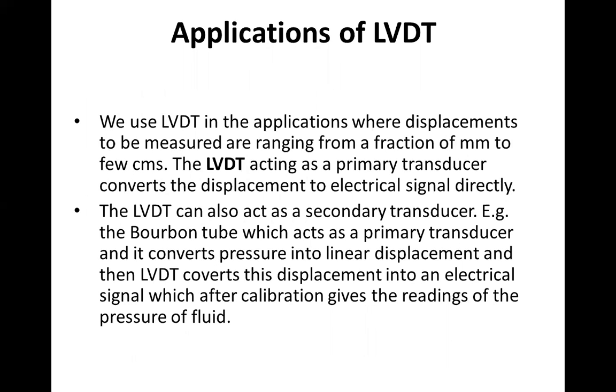Applications of LVDT. We use LVDT in the applications where displacements to be measured range from a fraction of a millimeter to a few centimeters. The LVDT, acting as a primary transducer, converts the displacement to electrical signal directly. The LVDT can also act as a secondary transducer. For example, the Bourdon tube acts as a primary transducer and converts pressure into linear displacement. Then LVDT converts this displacement into an electrical signal, which after calibration gives the readings of the pressure of fluid. So this is all about linear variable differential transformer.